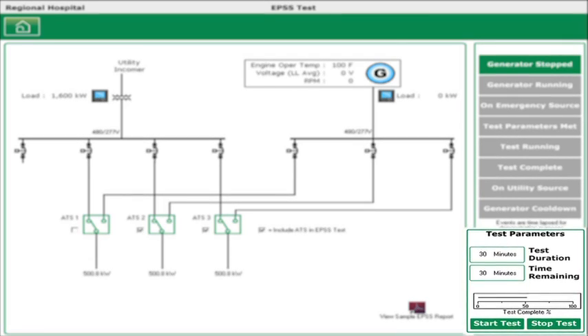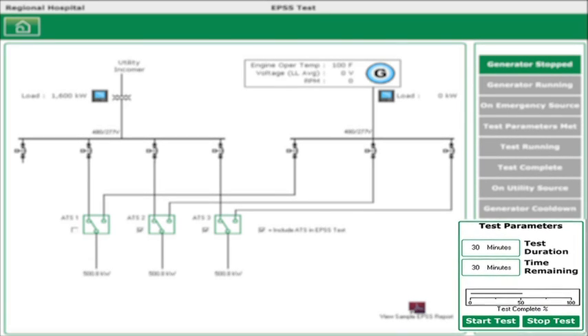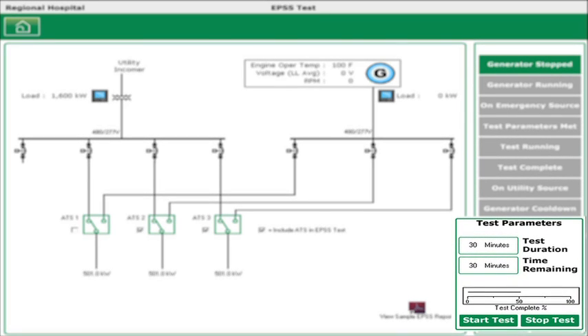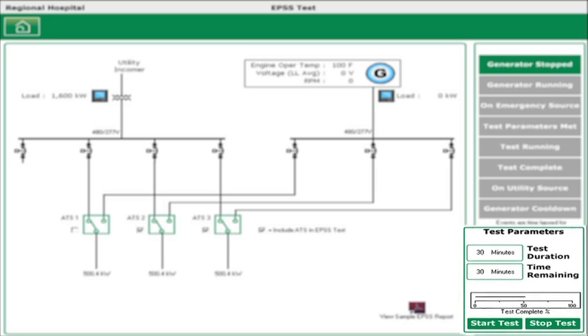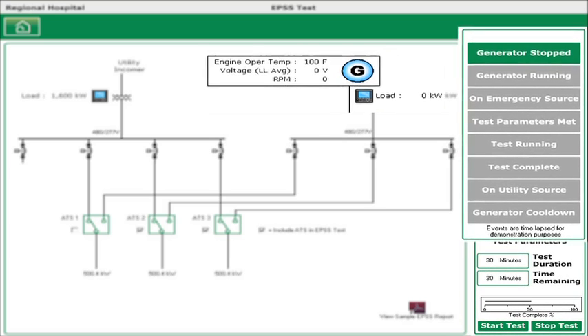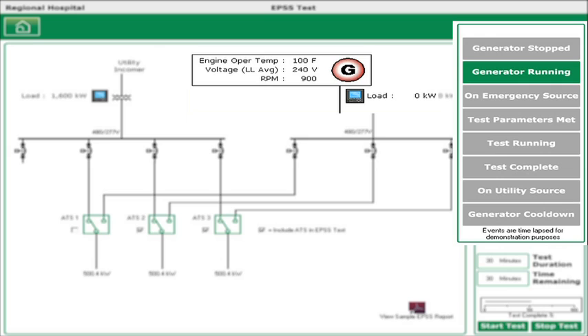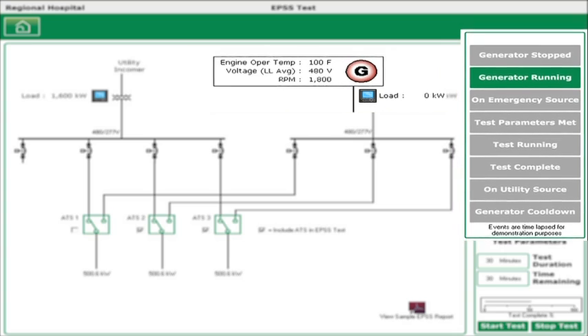The first step in the testing process is to initiate the test by switching the chosen lead automatic transfer switch to test mode, either directly or through the software. This triggers the generator to start. The test screen allows you to see generator operating details and ATS status in near real-time.